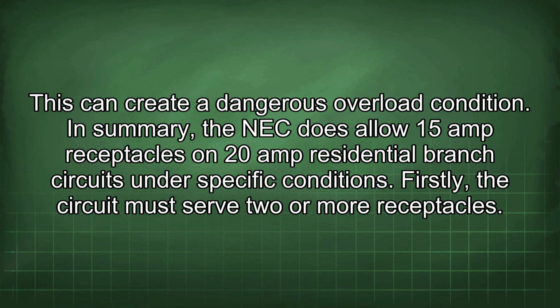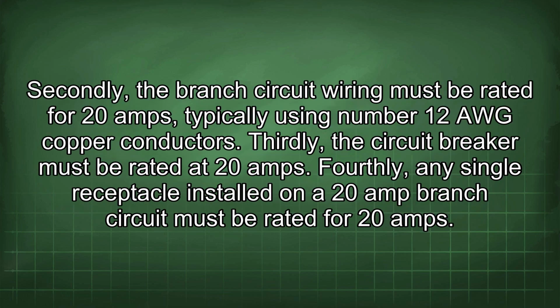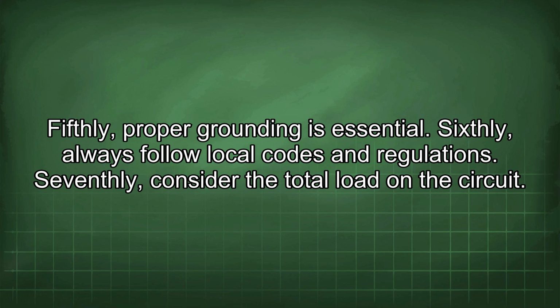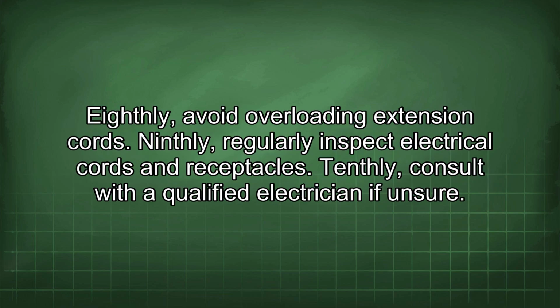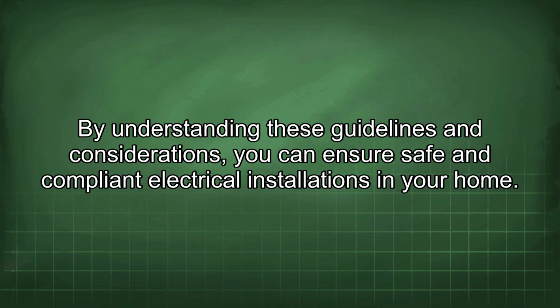In summary, the NEC does allow 15-amp receptacles on 20-amp residential branch circuits under specific conditions. Firstly, the circuit must serve 2 or more receptacles. Secondly, the branch circuit wiring must be rated for 20 amps, typically using number 12 AWG copper conductors. Thirdly, the circuit breaker must be rated at 20 amps. Fourthly, any single receptacle installed on a 20-amp branch circuit must be rated for 20 amps. Fifthly, proper grounding is essential. Sixthly, always follow local codes and regulations. Seventhly, consider the total load on the circuit. Eighthly, avoid overloading extension cords. Ninthly, regularly inspect electrical cords and receptacles. Tenthly, consult with a qualified electrician if unsure. By understanding these guidelines and considerations, you can ensure safe and compliant electrical installations in your home.